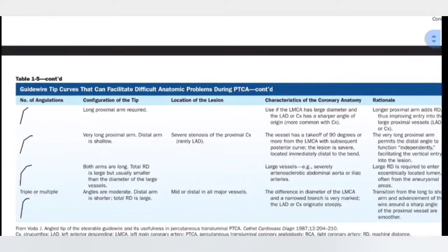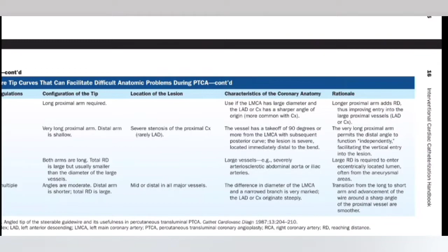For this double angulation guide wire tip curve, the number of angulations is still double, and the configuration of the tip is that a long proximal arm is required. It is used if the LMCA has a large diameter and the LAD or circumflex has a sharper angle of origin, more commonly with the circumflex.